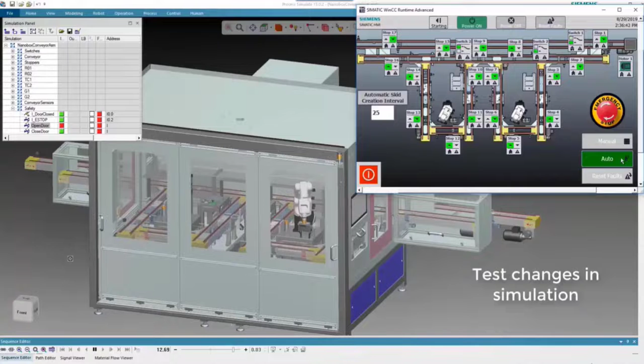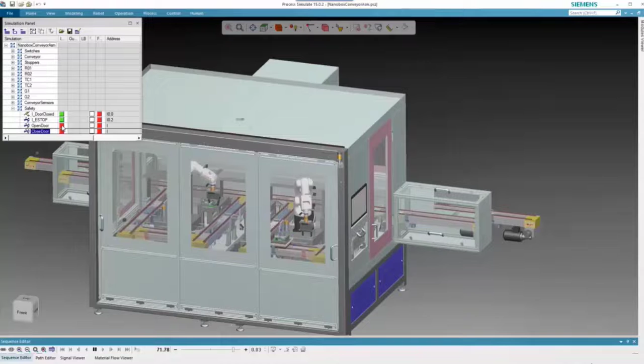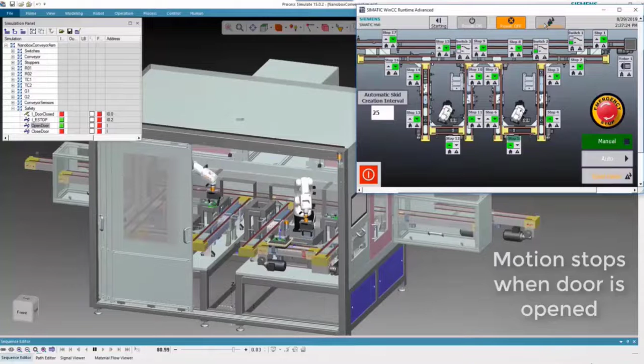This time around, when we power on the sequence and put the cell into automatic production, we can see that opening the door, as expected, makes production stop entirely. The operator also cannot reset this fault unless he clears the door again, meaning closes it and then hits the relevant button inside the HMI. This gives us a 3D environment realistic enough to test our safety situations in. The motion stops, and there's no way for the operator to do anything until it closes again.